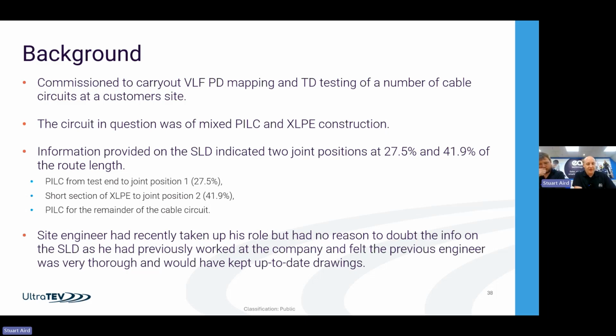So when we're doing these offline tests, or the online ones if we've got the access, we do need to ensure that we're locating every partial discharge and confirming whether it's in the XLPE section or a paper insulated section of the cable.